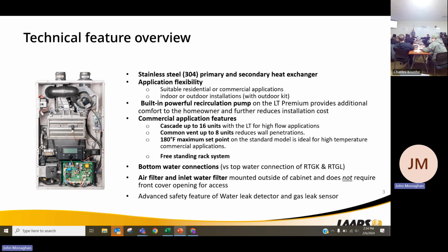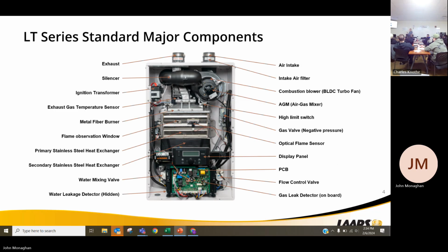This also has a water leak sensor, so if there are any internal water leaks, it's going to shut the unit down to alert the end user, and it also has a gas leak sensor. All of our components, this is going to be the standard model with no recirc pump: your air intake, your combustion blower, your mixing valve, your gas sensor, optical flame sensor instead of a flame probe, your burner, and your water leak detectors at the bottom. There's also a built-in mixing valve.